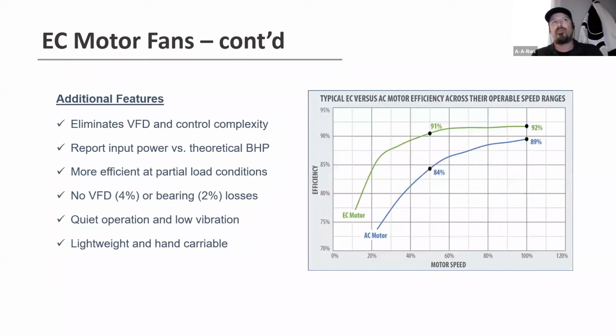And then we talk about motor efficiency. You'll see like Baldor, Marathon, and the like, they'll say that their super efficient motors are anywhere from 88 to 90% efficient. And that's really at full load. Once you start putting a VFD on there, start slowing them down, the efficiency of those motors tend to fall off, counting the power transmission from that shaft to that wheel. When you're looking at an EC motor, those tend to be about 90 to 95% efficient at the motor.